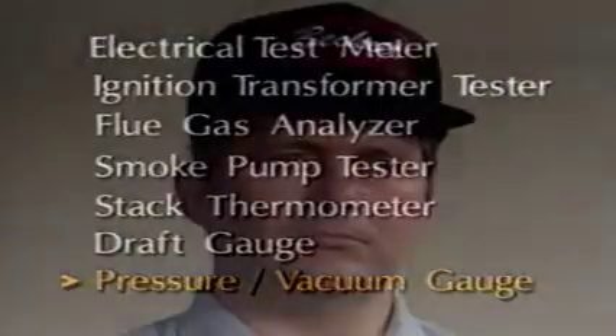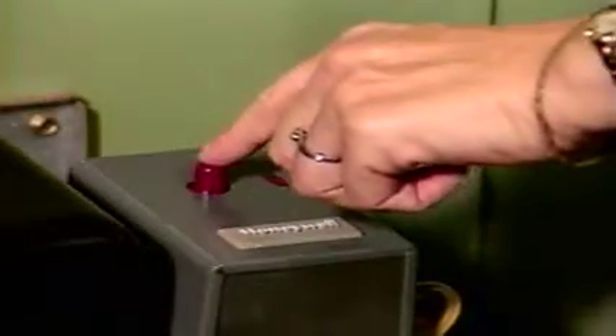But probably the most important instrument to begin with is this: your own ear. What did the homeowner tell you about the erratic operation of the appliance? Was there any unusual noise? Has this happened before? Was there any odor or smoke? And what about this primary control safety reset button? Did the homeowner push it in an attempt to restart the burner?